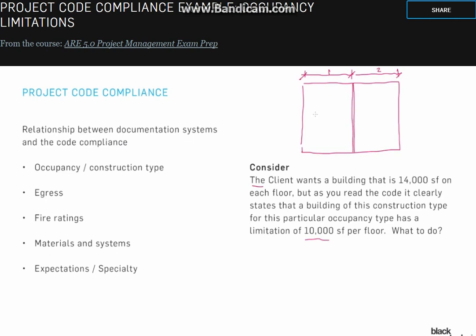And then when I have my corridor going right across from one side to the other, I would be able to have doors at this point, but I could just leave those doors open on some sort of hold-open element, like a magnetic system that's part of the alarm system, so that when the alarm goes off, those doors would close and make the continuation of that 4-hour wall.